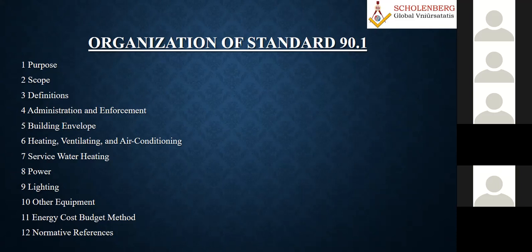But suppose the occupancy drops down. A school which was earlier planned for 50 students in a class is today having just say 15 students. We are having occupancy sensors, so the BMS system reads, okay, now I need to provide just the fresh air for those 15 students, and that outdoor air reduces. In that case, should I size my equipment, the terminal unit, for those cases as well? Because in those cases you must have also gone for a VAV system, isn't it?